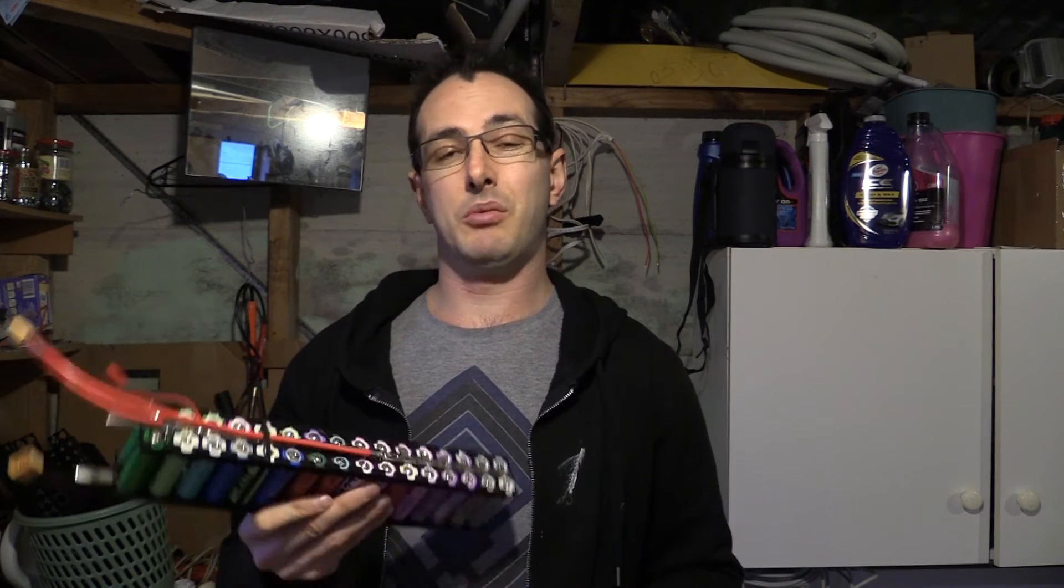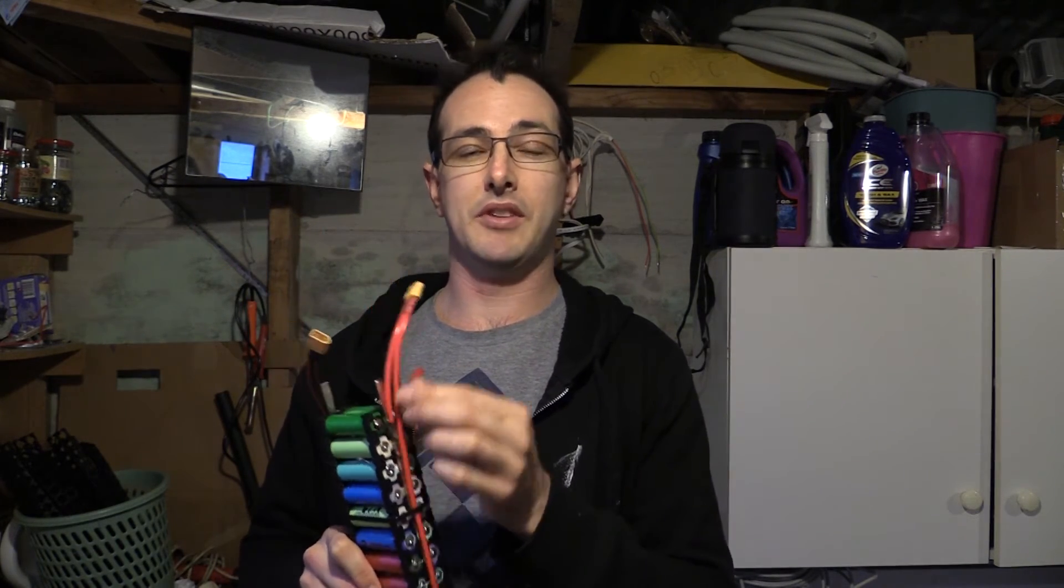Yeah, we might get to 27 amps, but that's still under 32 and it's still under 50 for the cables and it's still under 60 for the connectors. So because our voltage is much higher, we can get away with using much thinner cabling and much easier plugs to deal with.